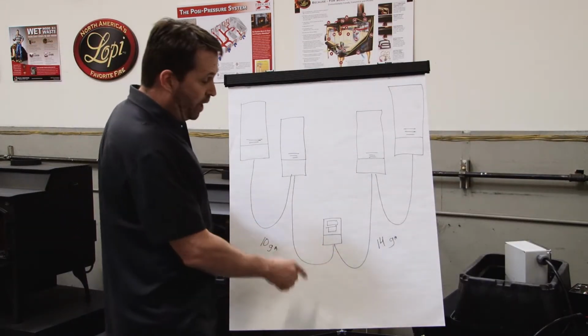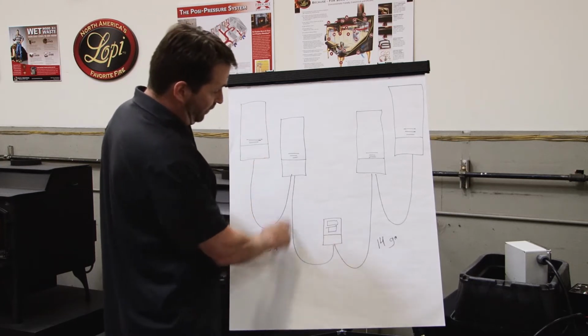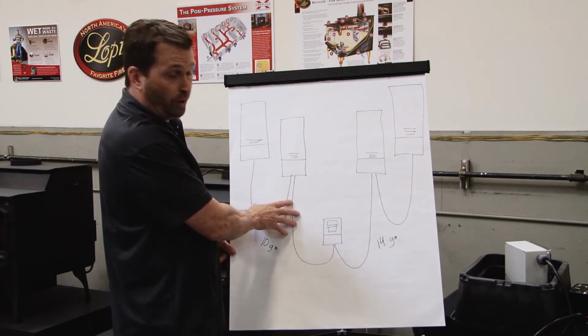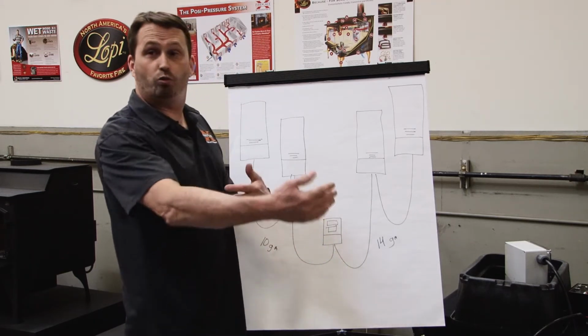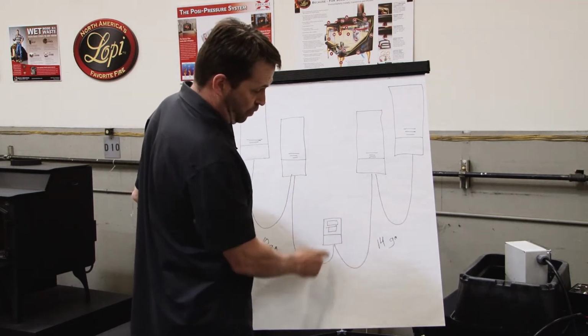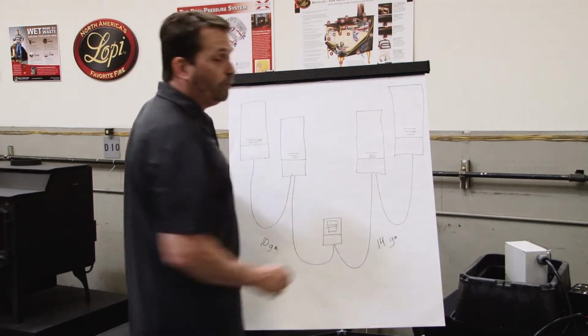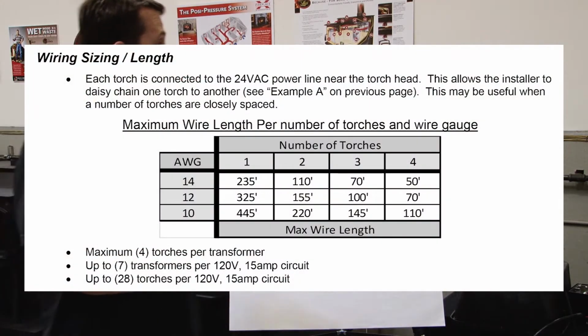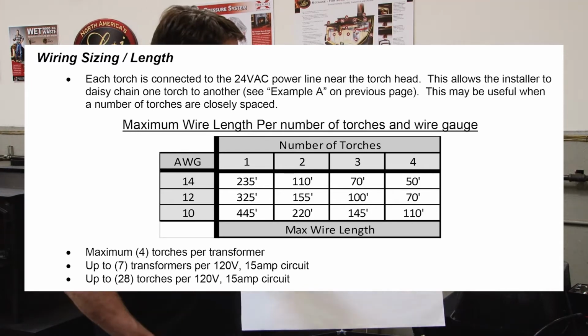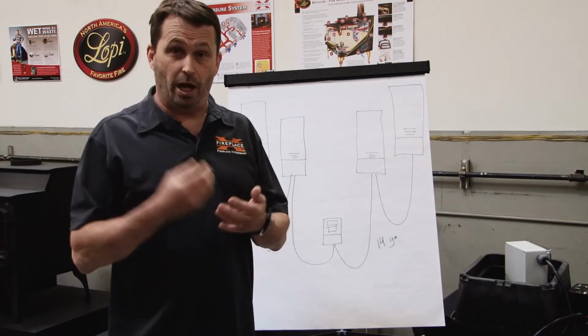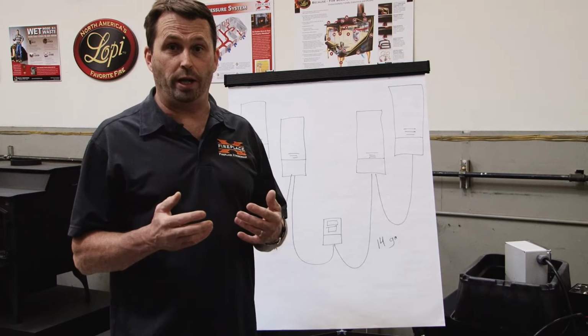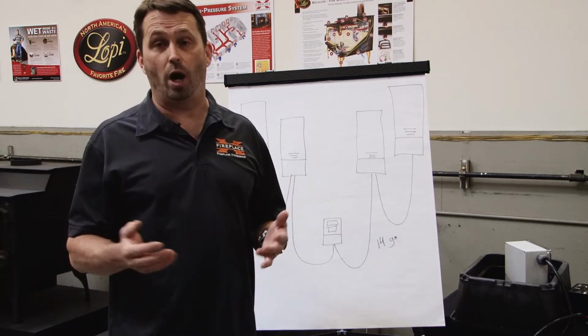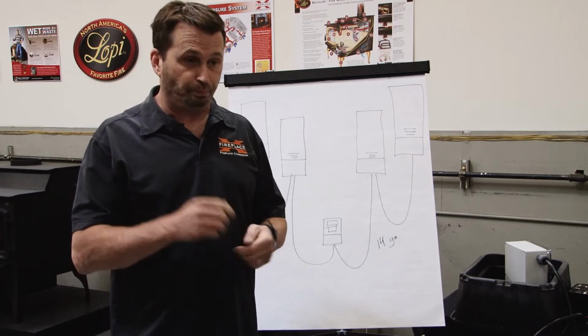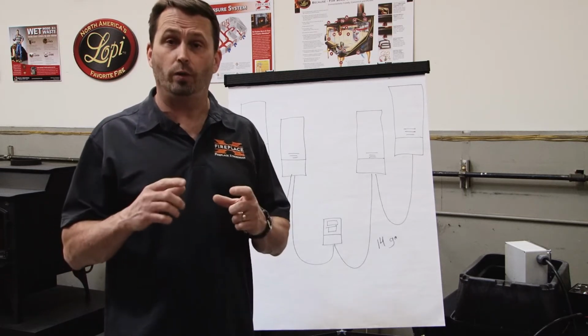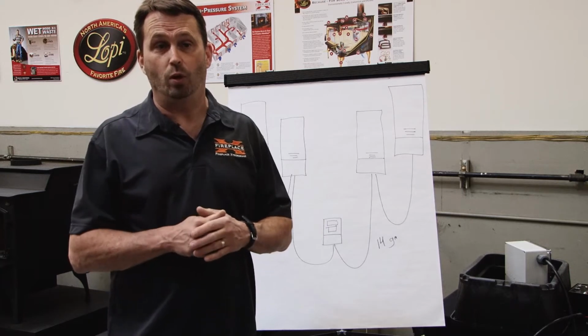So on this diagram here, we have 2 runs from the transformer. We have this 10 gauge run out, maximum 220 feet. On this one, the torches were much closer, so we did a 14 gauge run. So we daisy chain these. On a 14 gauge run, if you look at your wire chart, you should understand that the total length of these wires can be 110 feet. So it's really critical that you understand the relationship between the wire run and the gauge of the wire when you're dealing with low voltage wire. Make sure that you adhere to the chart that we provided in the installation manual.